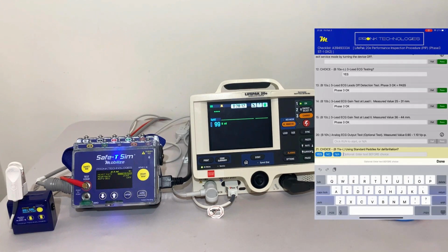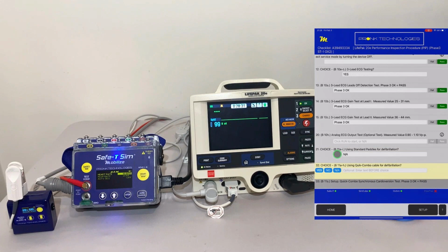If your facility doesn't happen to be utilizing the defib paddles, some do, some don't, we want to decide if we're going to run that test. In our case, we're going to skip doing the paddles test for this demonstration. The testing involves the same test. We're going to skip the paddles test and proceed on to do the defib discharge or shock test using the QUIK-COMBO cable. So I'm going to select yes here.